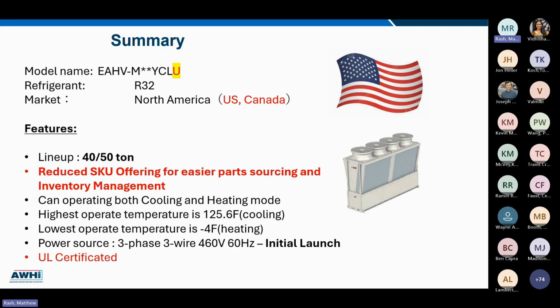The CHV doesn't have that limitation. With basic city multi controls with a remote controller, we can set up a group leader, and basically it can handle staging and lead lag of up to 16 modules to meet a combined blended water temperature set point target. We provide the water temperature sensors, and the system manages that automatically without any additional DDC controls.